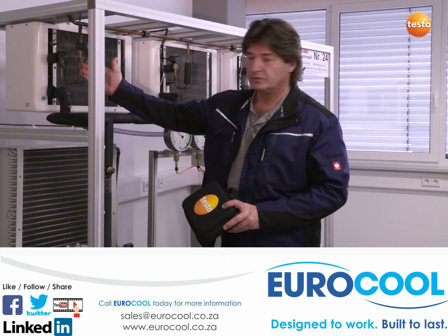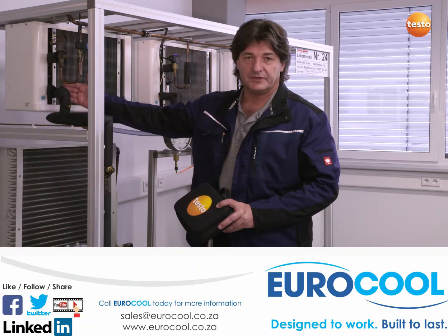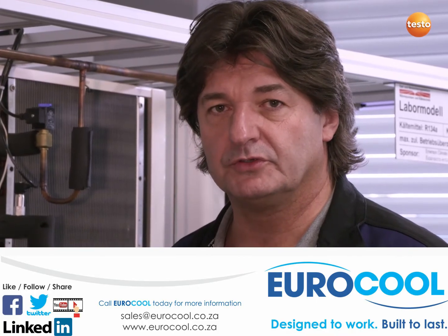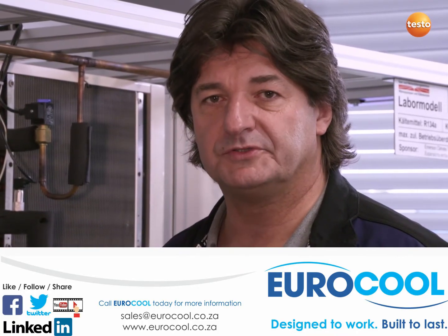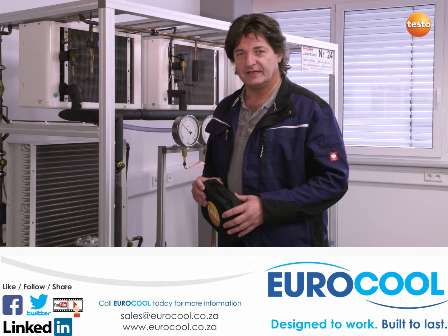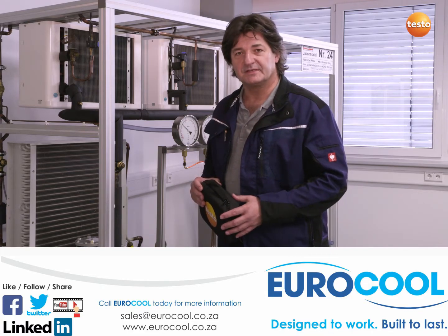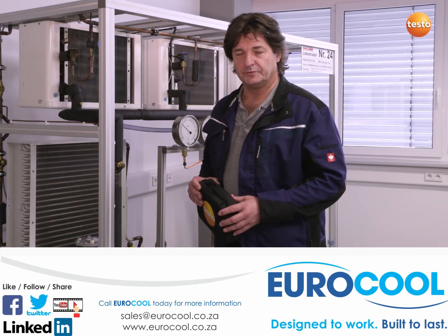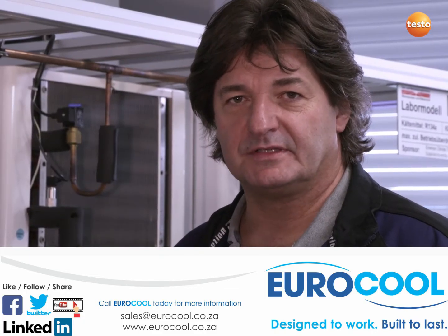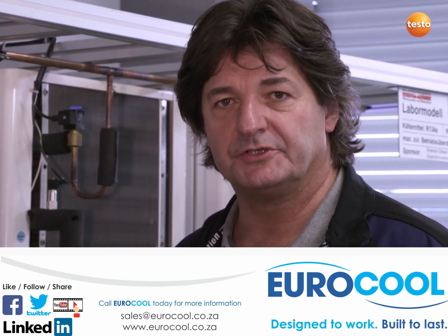The measurement shows me that in this case we have sufficient subcooling of the liquid before the expansion valve, but the evaporator superheating could maybe be improved a bit more. I am really impressed with how quickly and accurately I have been able to take a measurement, create complete documentation on site and send it as well. The stable radio links are extremely beneficial when the measuring points are far apart, for example in larger systems — it means that measurement cables are unnecessary, as well as hose connections filled with refrigerants. Incidentally, this is also an excellent aspect from an ecological point of view. I am certain that the Testo Smart Probes refrigeration set will help me considerably in my daily work on refrigeration systems in the future.